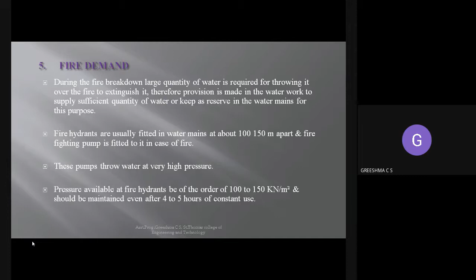The pressure available at a fire hydrant should be of the order of 100 to 150 kilonewton per meter square, and it should be maintained even after 4 to 5 hours of constant use. While designing a fire hydrant, it is designed in such a way that it throws water at a very high pressure, varying between 100 to 150 kilonewton per meter square. This is the pressure with which water is pushed.